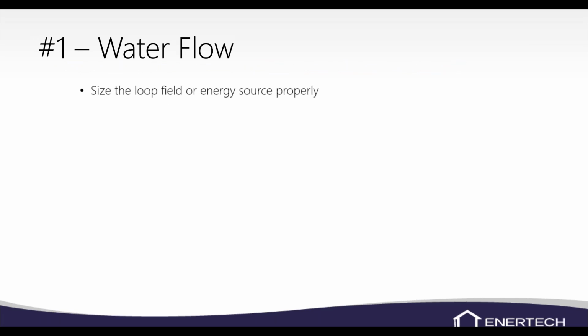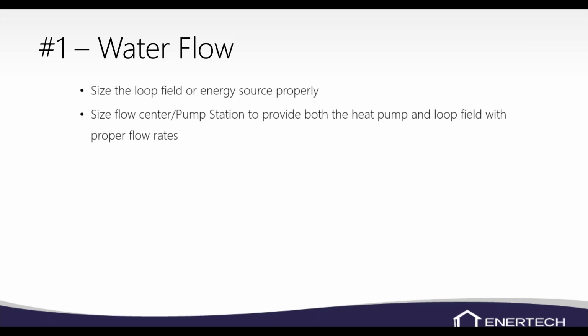So water flow, again, we've got to size the loop field and energy source properly. We also have to size the flow center properly as well. We can't really throw a single pump flow center on a 7-ton unit. We're not going to have enough water flow. So we've got to make sure we've got enough pump and we've got enough pipe in the ground to be able to transfer our heat properly.